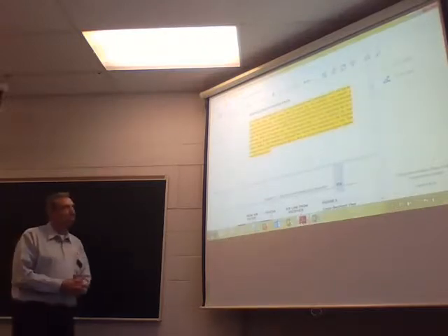So a suction line unloading valve, shown in figure 3, is inserted into the intake valve and shuts off the air from the inlet valve. When the pressure in the receiver rises above a predetermined point, the small piston is actuated by the pressure in the receiver against the resistance of the spring. When the pressure in the receiver becomes too high, the piston is moved sufficiently to open a small port, admitting air into the plunger valve. On the larger area, this plunger valve is forced down.